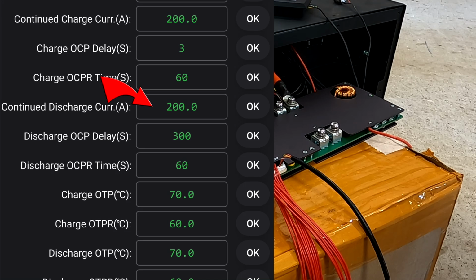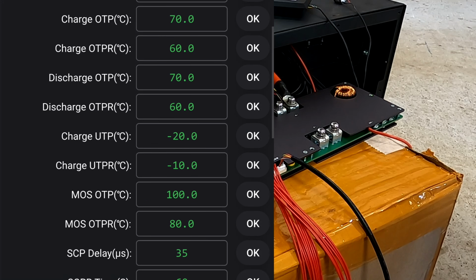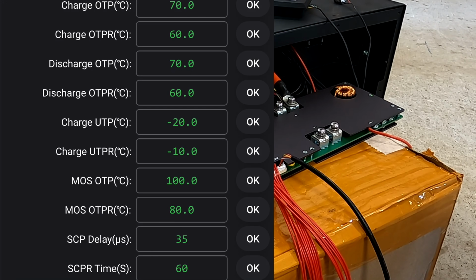And we have exactly the same functionality for the discharge current as well. Discharge current is 200 amps. The delay here is 300 seconds. And then it waits for 60 seconds and checks again if the discharge current is still above 200 amps. And then we have a whole bunch of temperature protection and recovery settings you can put in.